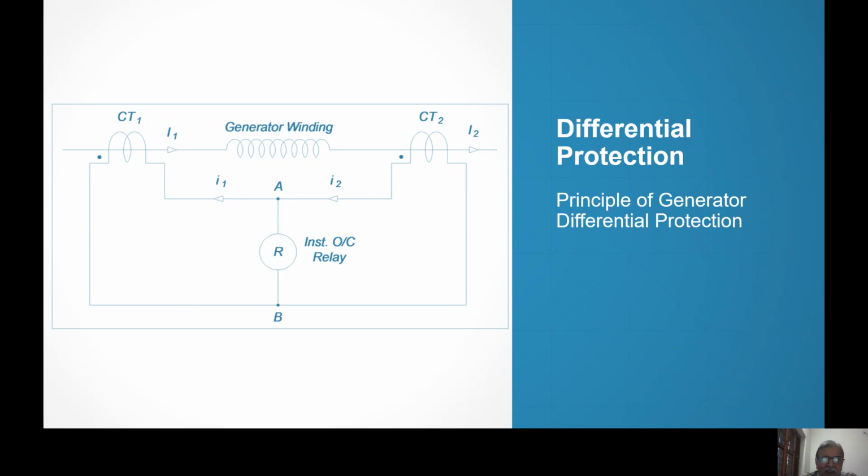And if you calculate the fault current as per the rule 3 E_ph upon Z1 plus Z2 plus Z0. Z1, that is the subtransient reactance, because you should think of the worst case, that is 20%. And for 210 megawatt, it is roughly 0.2 ohms. The negative sequence reactance is also of the order of 20%. Zero sequence is hardly 10%. So 0.5.